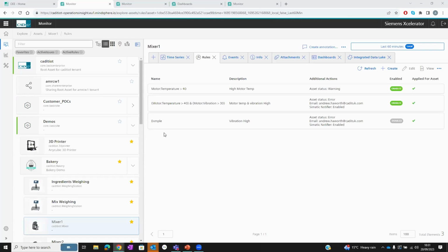So there's really two elements to this that have come into play here. We've got OEE, which is signposting there's a problem. We've got drill down into that problem, which can highlight that there's a particular asset that's at fault. The engineer's got the data to analyze that asset and see values on the mixer, see incidents that have occurred on that mixing process, and they make a determination by centering in on the motor of what to do next, and then highlight the action that's been taken.